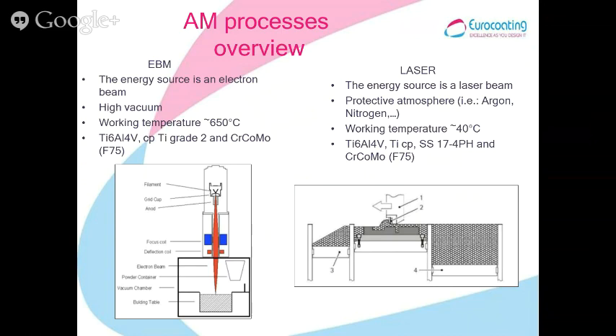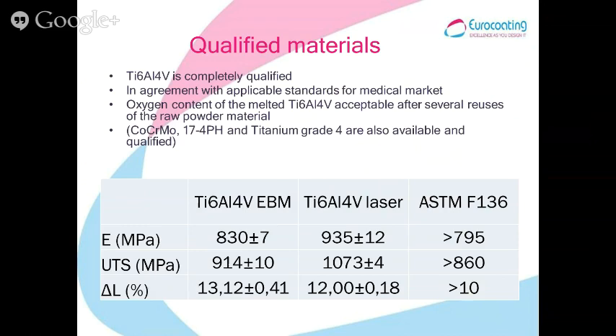Neurocoating is equipped to work with titanium 6-4 and also with grade 2 and cobalt chromium for EBM. The laser process, on the other hand, is a low energy process compared to EBM, low temperature, and works in a protective atmosphere. Eurocoating is able to work with titanium 6-4, pure titanium, stainless steel 17-4 PH, and cobalt chromium for laser.